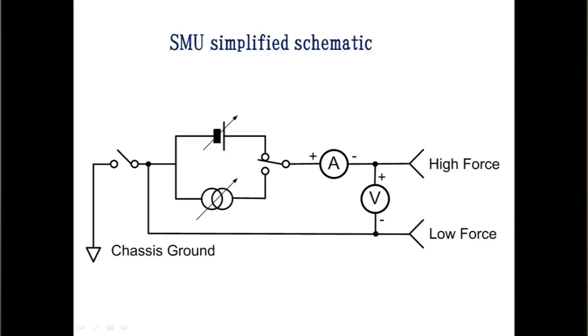Let me show you how to measure voltage with high input resistance by using source measure unit, SMU. SMU can force voltage or current and measure voltage and current simultaneously. In this demonstration, current force and voltage measurement mode is used.